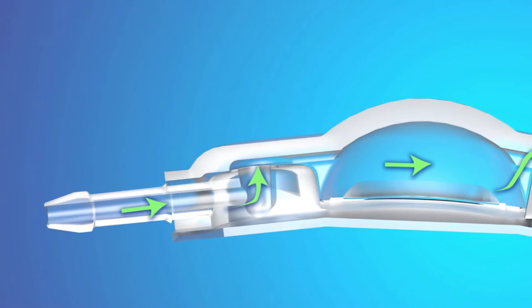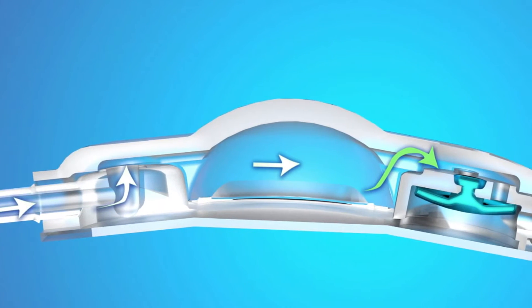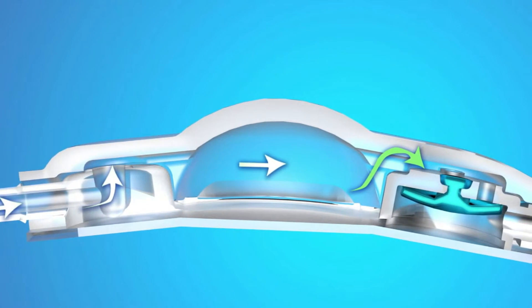As CSF flows through the Delta Valve, it enters the inlet connector, flows by the proximal occluder, and into the central reservoir. For sampling CSF, the reservoir dome can be accessed using a 25 gauge or smaller non-coring needle.